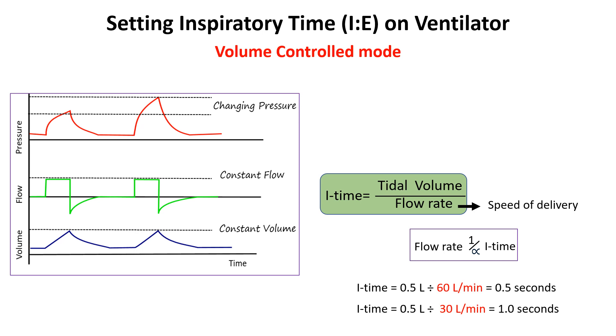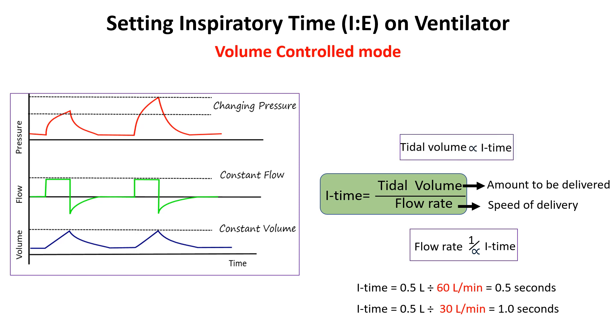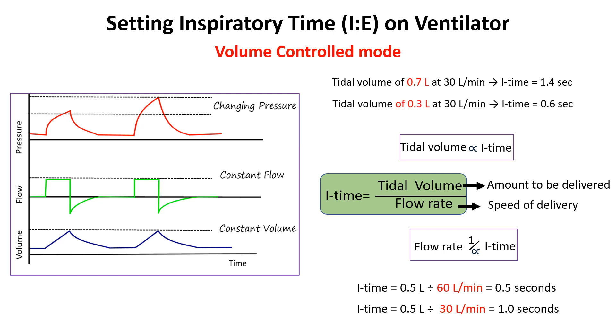Tidal volume is the total volume of air delivered during inspiration. While the tidal volume is set, its impact on inspiratory time comes into play indirectly when adjusting the flow rate. Larger tidal volumes require more time to deliver if the flow rate remains constant. For example, a tidal volume of 0.7 liters at 30 liters per minute results in an inspiratory time of 1.4 seconds, while 0.3 liters at the same flow rate results in 0.6 seconds.